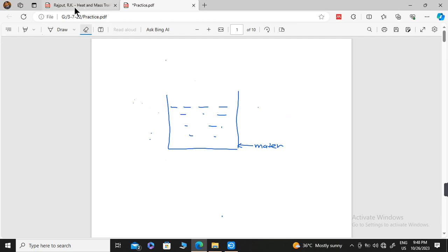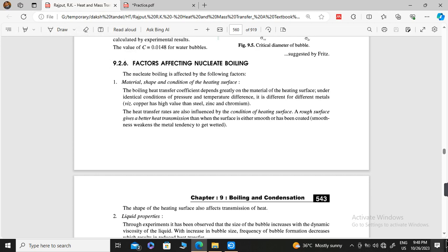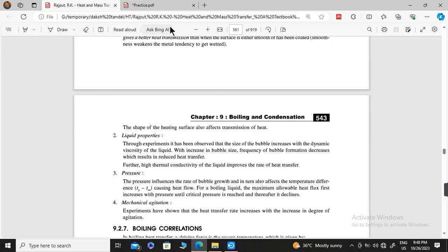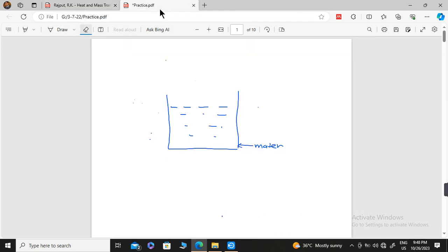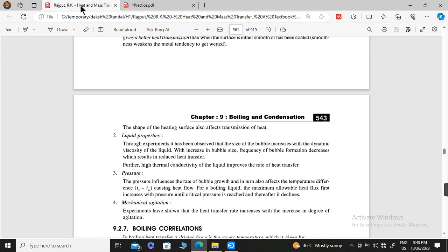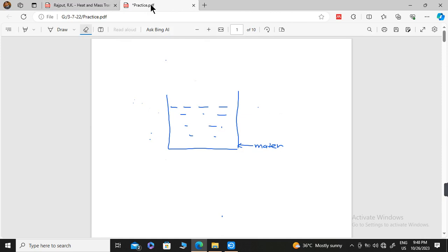Another factor is liquid quality — whether the liquid is water, oil, or another type of liquid. Pressure is also a factor. For example, in a pressure cooker, steam generates pressure inside, which is known as pressurized heating. At atmospheric pressure it is one bar, but it can be two bar or more — this affects nucleate boiling. In process heating boilers it may be 15 to 20 bar, and in power plant boilers it can be 50 bar, so pressure significantly affects nucleate boiling.